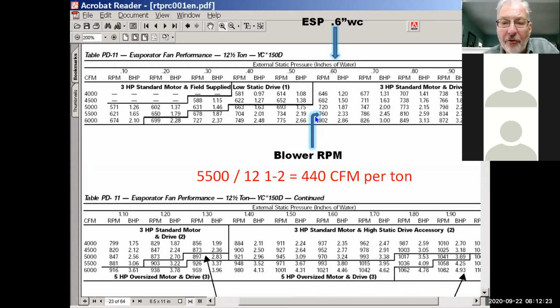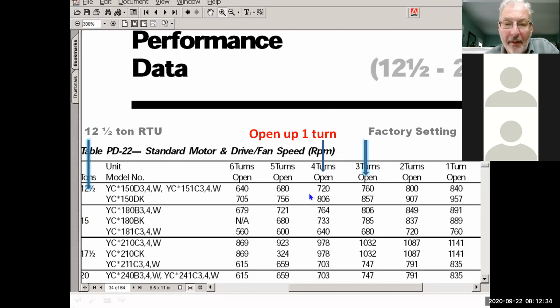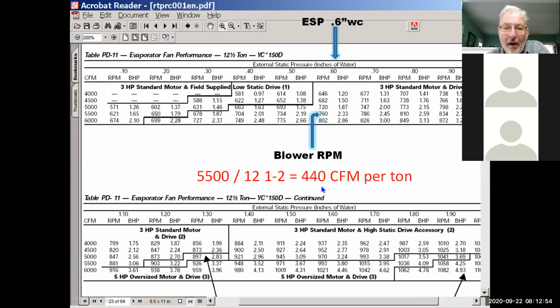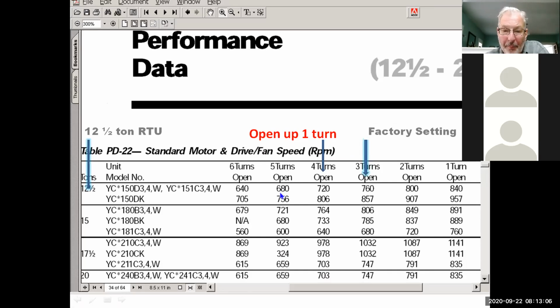So what we want to do is change that to get down to 5,000. And in order to do that, we have to take that pulley down to 720 RPM. And if you look at the performance data, 720 RPM means that pulley needs to be open 4 turns. So on a low static or a fairly normal static situation, you may actually have to slow down the blower from that 3 turns open to 4 turns open. If I want to go lower, if I want to take it down to 4,500, which is 682 RPM, I may want to take it to 5 turns open. And the only time you want to do that is if you're looking for better dehumidification. So now we're down to about 350 to 360 per ton. It just changes the dehumidification. But that's basically what this chart tells us.